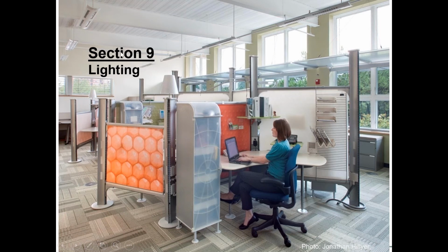That's one of the big things that the energy code is pushing us to do: use more natural daylight in spaces where it makes sense, and then have any light fixtures that are in what's called the daylit zone, and pretty much everything you see in here is the daylit zone, have controls to automatically dim them, as you might expect. So that kind of makes sense. And then of course, these are east-facing glass, where in the morning when the sun is hitting them, there are blinds that can shade it, but in the afternoon the sun gets overhead and those can just retract or open fully. So anyway, kind of a neat thing.